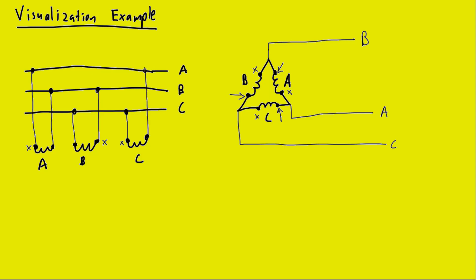Now you may stop and say, well, we already have connections at those points. But you see, what we talked about with the delta construct is there are two connections necessary for every single line. We have three incoming power lines, but six total connections.